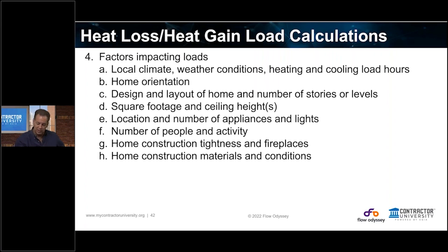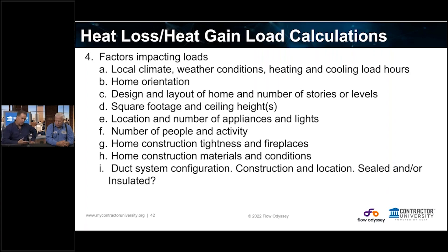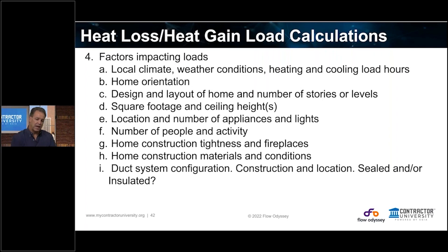Home structure tightness — it allows for infiltration and exfiltration. The home construction materials and the condition of those things matter. We talk about looking at an attic and saying maybe they have R-30 insulation there, but in some spots it dips down to three inches. What is the condition of the insulation? Is it relatively uniform? Use your best judgment. The duct system — what is the configuration? Where is it installed? Is it part of the conditioned space? If so, I can eliminate the duct loss and duct gain. If going ductless mini splits, I also remove duct loss and duct gain from the calculation.